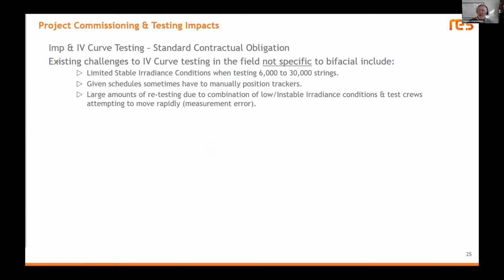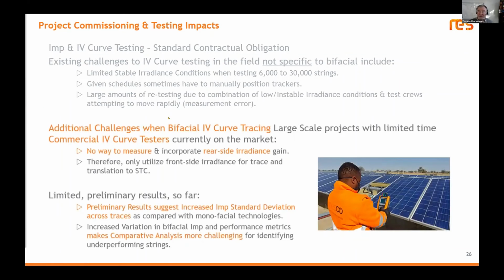Accelerating a bit, there are a few more considerations: the impact on maximum current and IV curve testing, plus standard contractual obligations. With bifacial, there are new challenges too, because commercial IV curve testers can't measure rear side irradiance gain, so you can only use front irradiation and translate it to STC values.